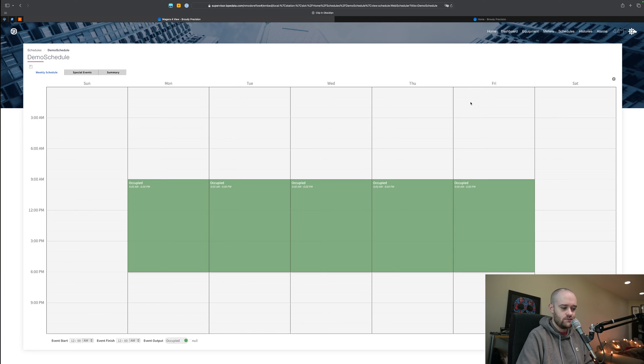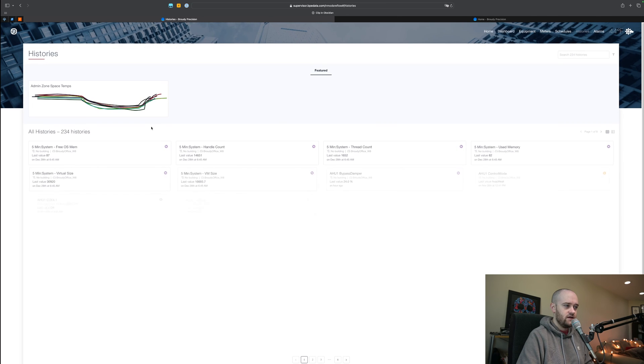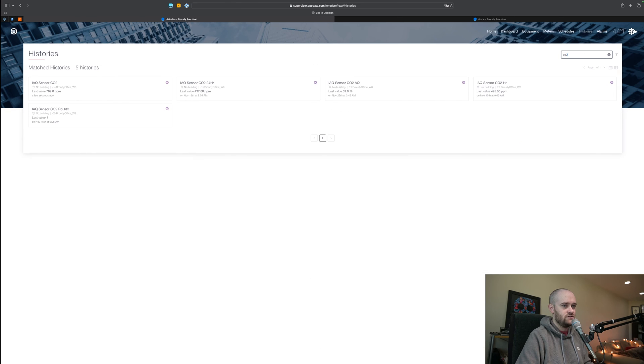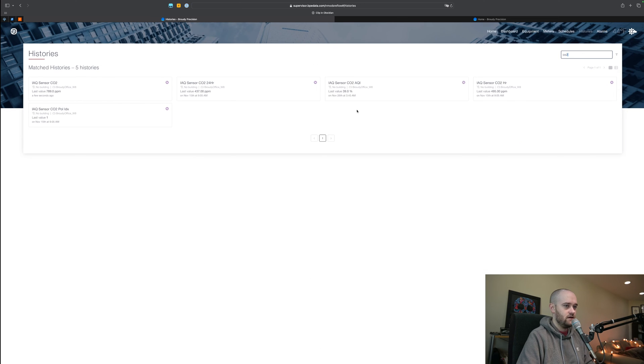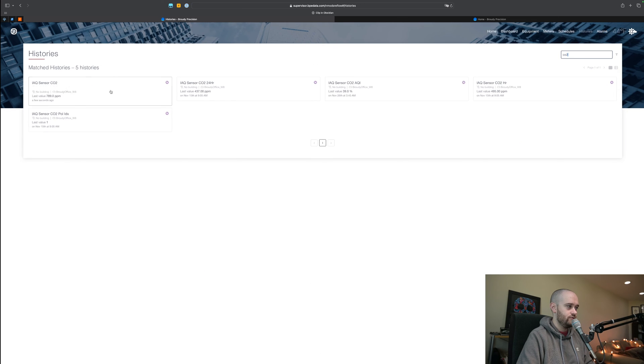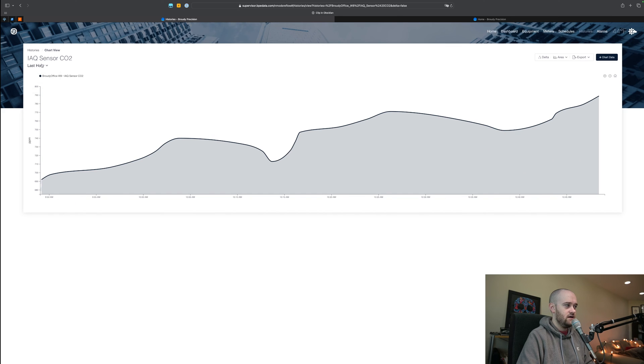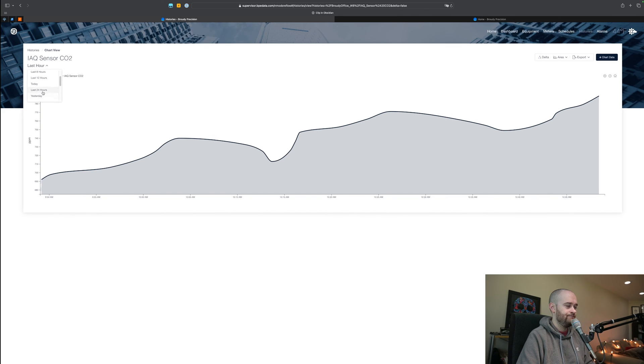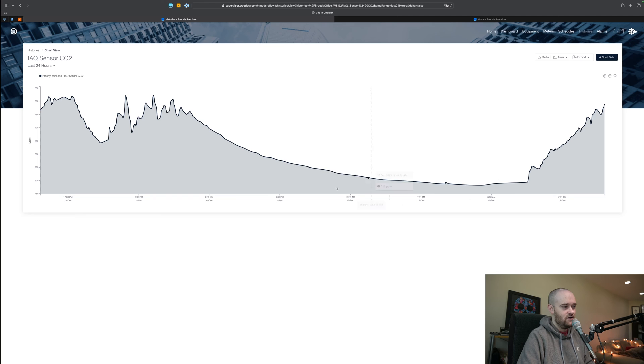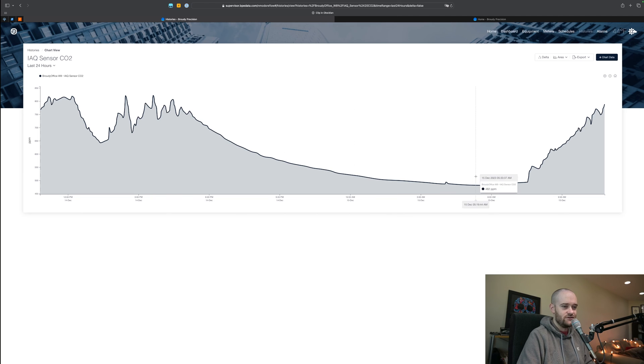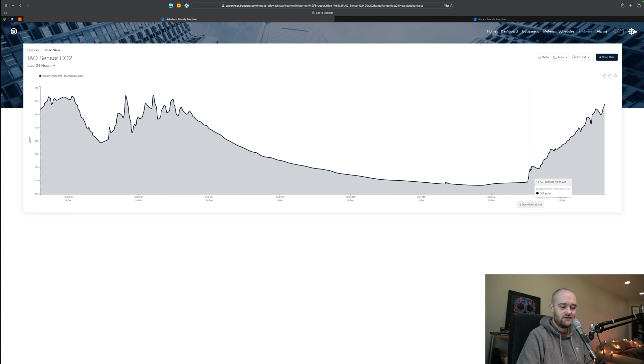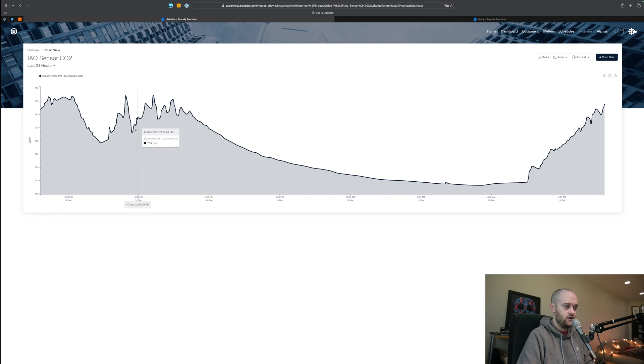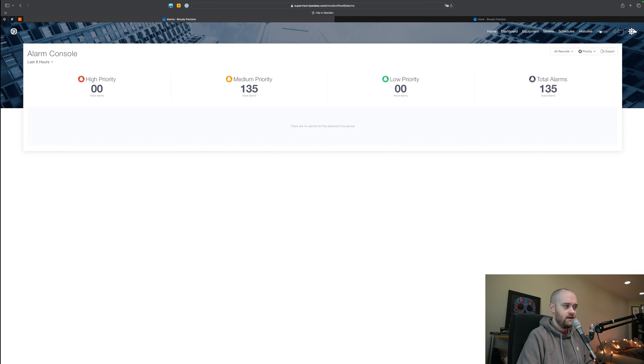Then we can look at histories. If I just pull up our CO2 history, we could take a look at the last 24 hours. You can kind of see when the building goes unoccupied and people leave, we can see our CO2 go down. Then it starts coming back up as people get in the building, strongly around 7:30, that kind of thing. Again, this is all Reflow's built-in charting features.